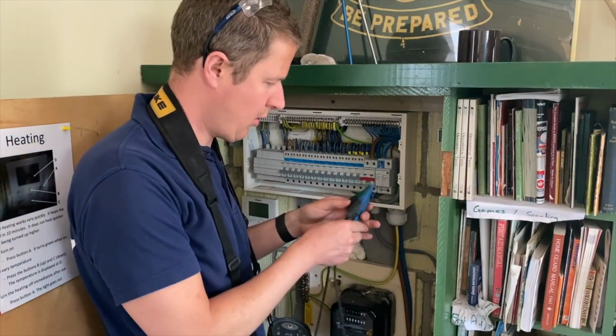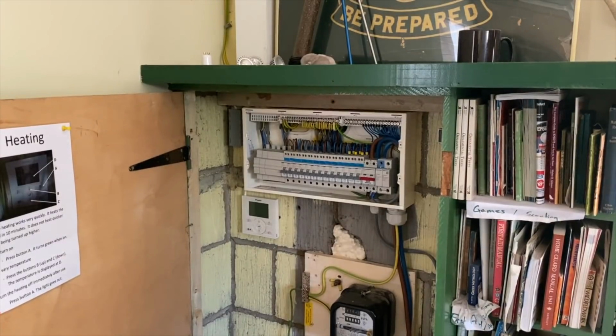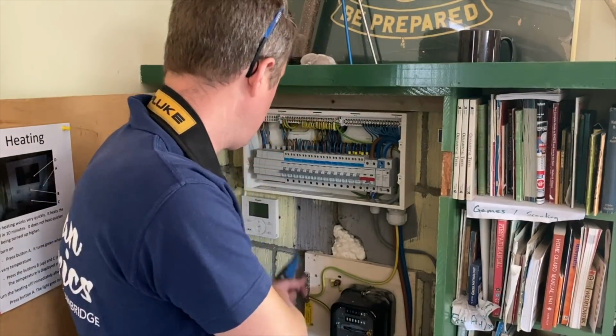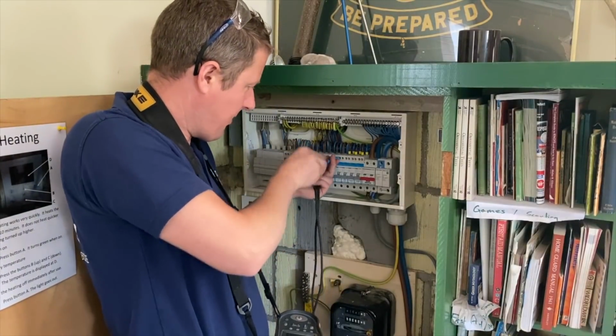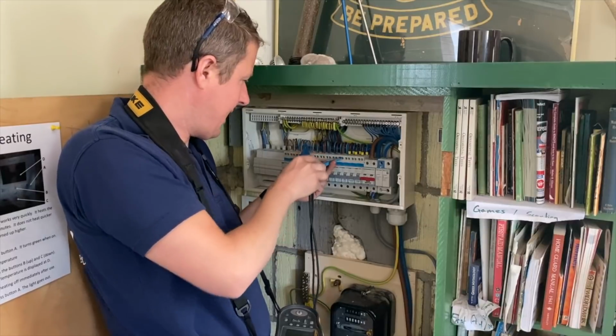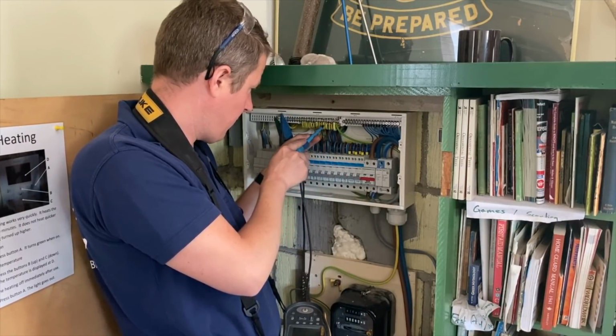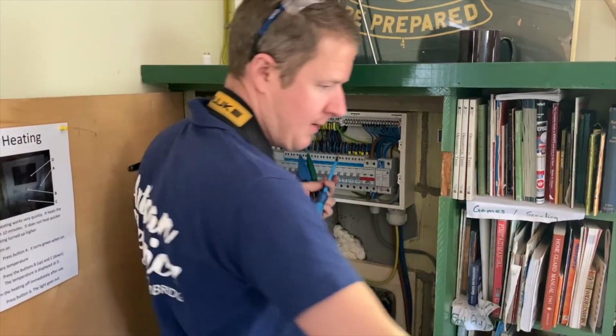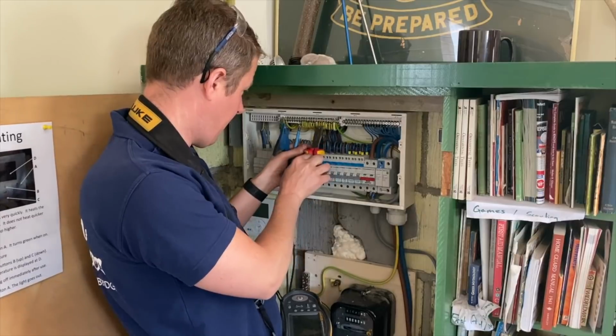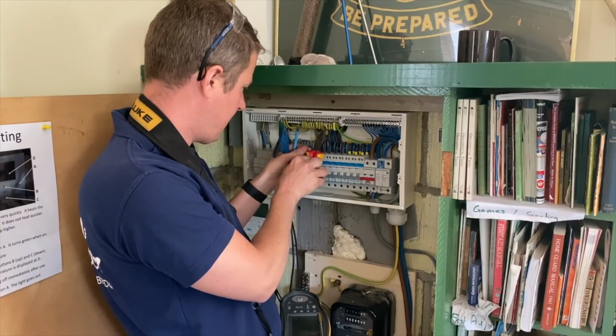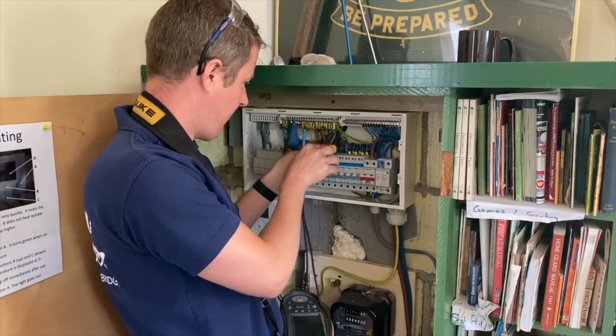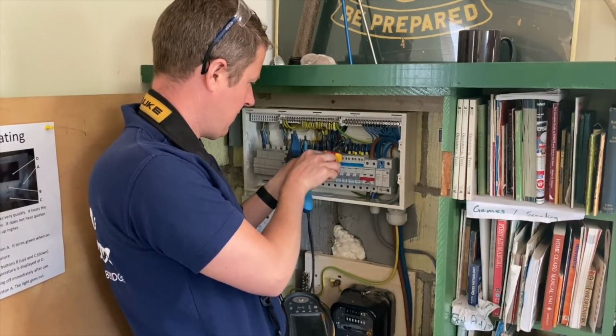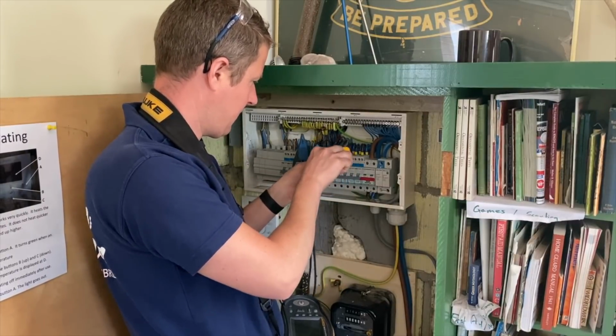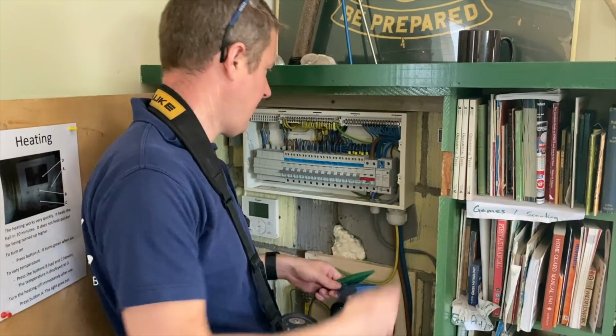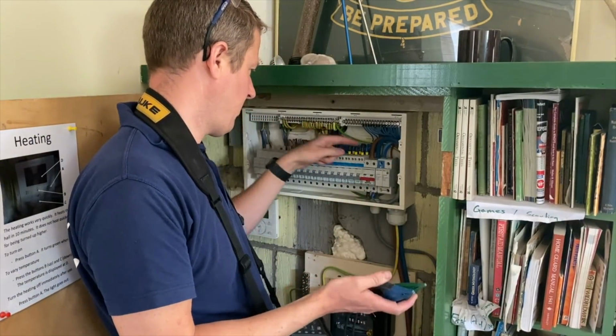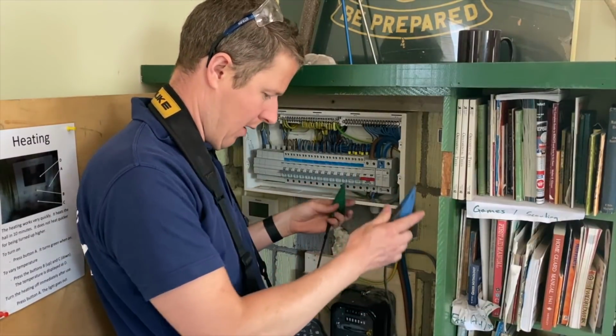For this I usually use 2 crocodile clips. And a pair of long nose pliers comes in quite handy on this test, just to neatly lever the things out. So that's circuit 4, so I go 1, 2, 3, 4 and it's this one for the CPCs. Nice pair of Knipex long nose pliers, and we can gently lever those 2 out. Like that. Same with the phase conductors, and same with the neutral conductors. This way it's easy to put them back in neatly, because I've made so much effort making sure the bend radiuses were all the same that if I just lash it out, it's going to ruin all my hard work.